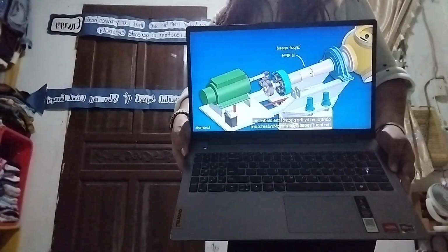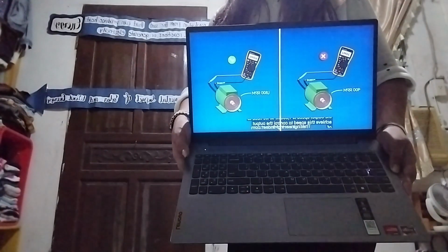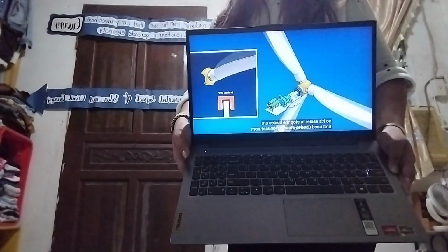The rotational speed is controlled by the pitch of the blades, so the input speed might be just 18 RPM, and the output speed is 1,800 RPM. We need to achieve this speed to control the output of the generator. We also have a hydraulic disc brake at the back of the gearbox because the shaft is low torque, so it's easier to stop. The blades are first used to stop the rotation. The brakes will then hold it in place, for example during maintenance.